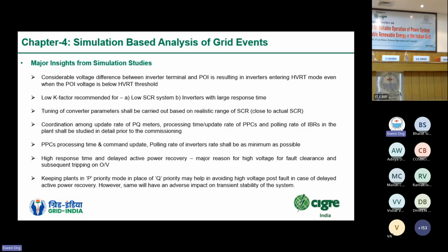Then we could recommend an appropriate K factor based on the system strength. Based on the simulation studies, what will be an appropriate K factor to be implemented in the RE plants? For low SCR systems and inverters with large response time, we had recommended different sets of K factor to achieve a desired response. Then converter parameters were tuned based on the realistic range of short circuit ratio. If inverters are tuned to a short circuit ratio of 20, 25, or 15, it will be very difficult to achieve such short circuit ratios in the operational horizon. And CEA standards also mention a short circuit ratio of not less than 5. So plants have to tune their inverters within the possible operating range, which could be near 5. That feedback was given to the developers based on the simulation study results.